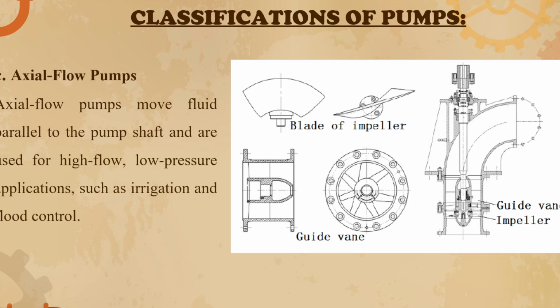Third classification of pump is the axial flow pump. It moves fluid parallel to the pump shaft and is used for high flow, low pressure applications such as irrigation and flood control. Shown on the right side of this slide is the axial flow pump and its components: the blade of the impeller, the guide vane impeller.